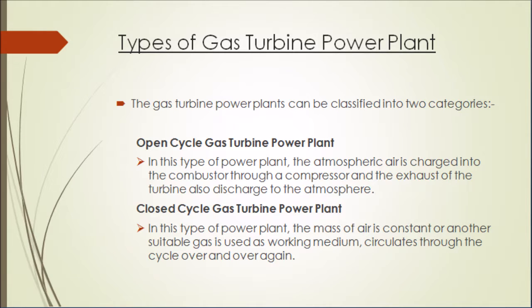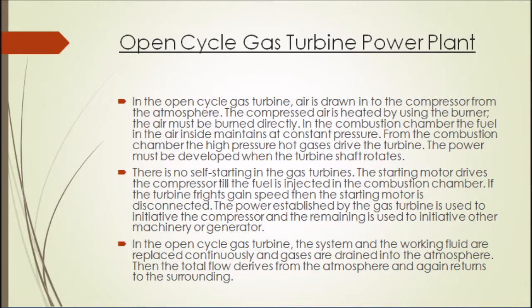So basically, there are two types of gas turbine power plant. One is the open cycle gas turbine power plant, and another one is the closed cycle. In the open cycle gas turbine, air is drawn into the compressor from the atmosphere. To compress air, it is heated by using the burner. The air must be burned directly. In the combustion chamber, the fuel and air inside maintain a constant pressure. From the combustion chamber, high-pressure hot gases drive the turbine. The power must be developed when the turbine shaft rotates. There is no self-starting in the gas turbine — the starting motor drives the compressor until the fuel is injected in the combustion chamber.